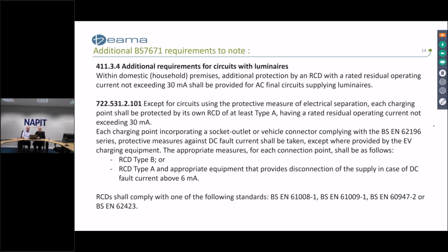And the other regulation that we'd like to point out is Regulation 722.531.2.101, where for electric vehicle charging applications, where an RCD is required, it shall either be a Type B, which was already in the previous version of the regulations, or Type A with appropriate equipment that provides disconnection of the supply in case of a DC fault current above 6 milliamps. Products complying with BS IEC 62955 meet the requirements for this additional appropriate equipment. So if you're using a Type A, you've also got to have a product to BS IEC 62955.